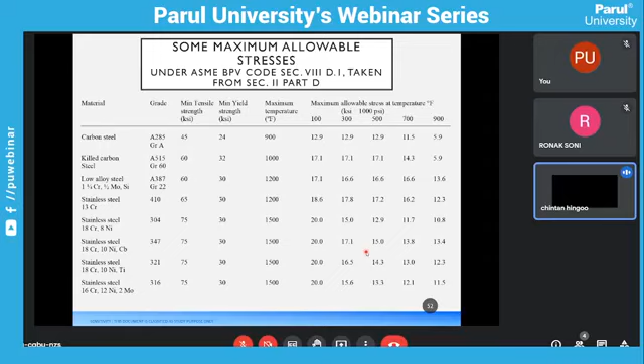Now, if you see carbon steel at 900 Fahrenheit, your allowable stress is nearly 5.9 ksi. But at the same time, if you use stainless steel material, your allowable stress would be 11.5 ksi. So you can further reduce the thickness, but at the same time, the cost will be higher with stainless steel. So optimization has to be done during the process as well as mechanical design. This entire thing is taken from ASME Section 8 Division 1 and ASME Section 2 Part D, which gives you material properties.